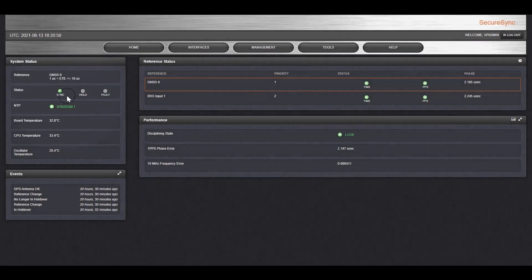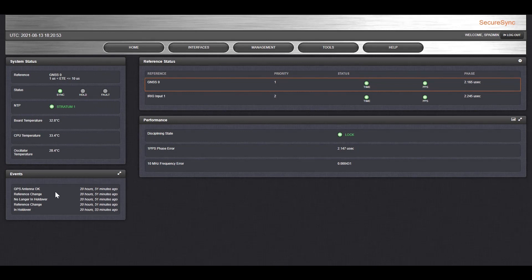Power status is normal, green is good, and it's not in a holdover or anything. Right below that, you can see the event history. You can see that we disconnected the GPS antenna 20 hours ago, and now it's been reconnected. This tells you exactly what's happened in your system. And you can also dive deeper and get details on each event or search for an event, for example, if you wanted to know if there was a reboot.